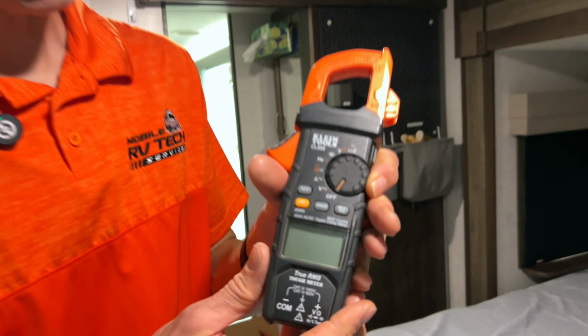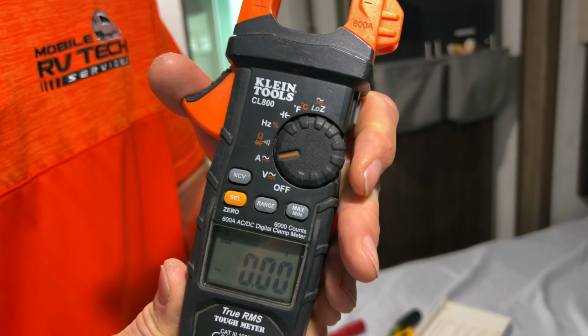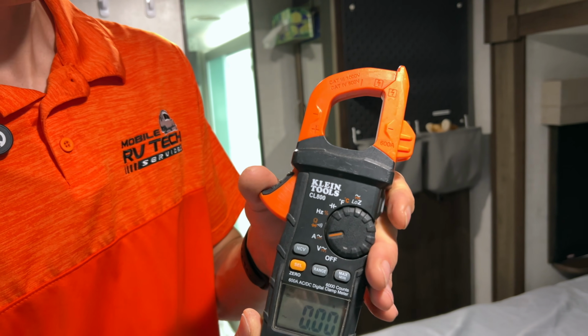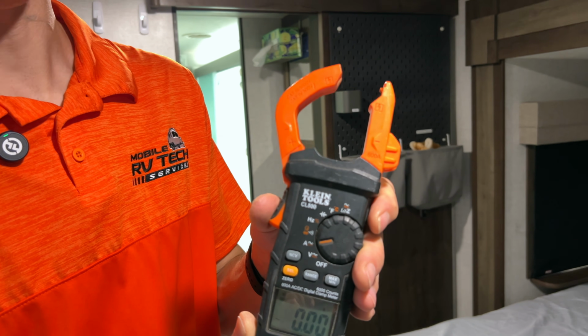Now what that 12.7 means is 12.7 amps when it's 95 degrees at the roof temperature. If it is less than that, you basically figure 1 amp less for every 10 degrees under 95 degrees. So if we are 75 degrees outside, we should see about 10.7 amps at 120 volts. So now I'm going to fire up the AC, put an amp meter on it, and see what it reads. And we'll take our multimeter, set it to amps AC. In this top portion up here, this is where the wire goes through. We'll open it up and put it around the blue wire.